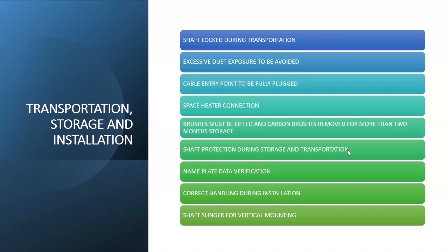The windings are heated regularly. So on a monthly basis, you have your checklist. You go and check whether the heaters are working. You check your insulation resistance, and you record it and keep it in the maintenance software you use in your area.